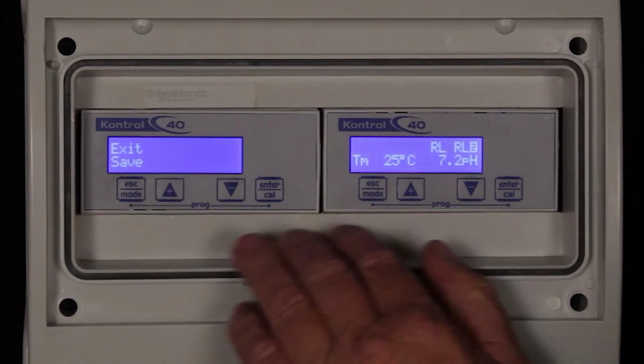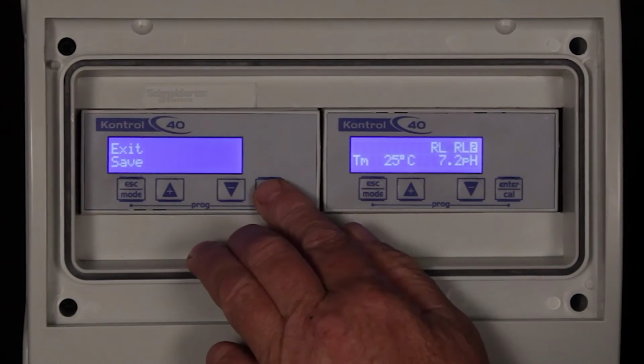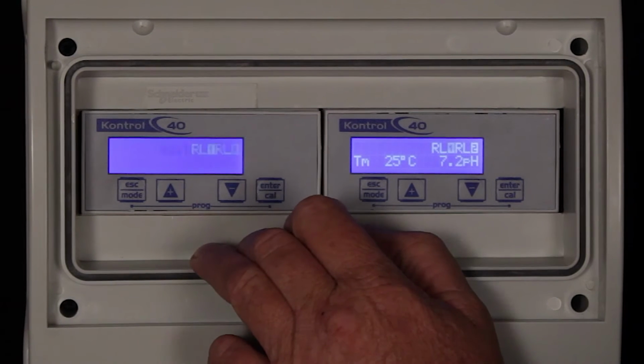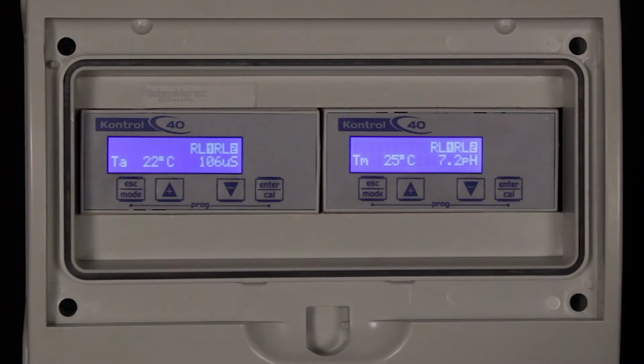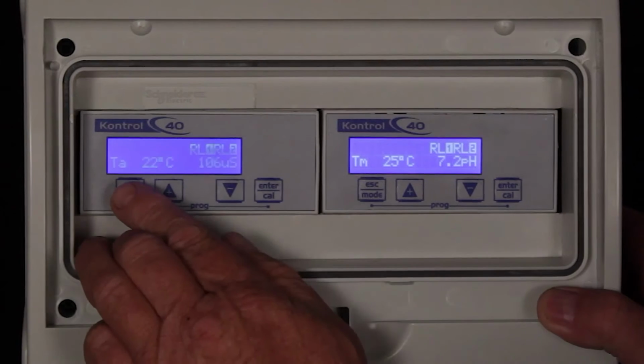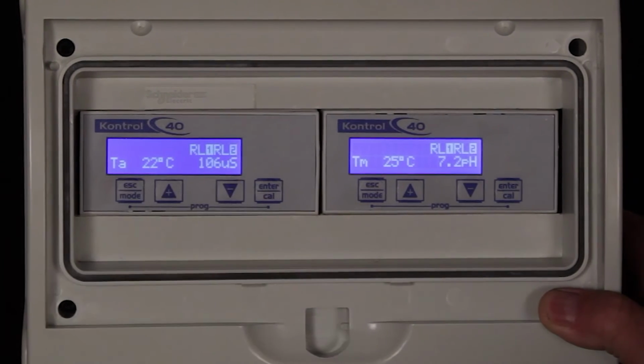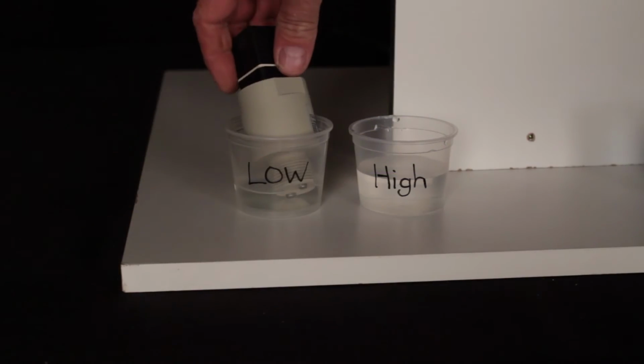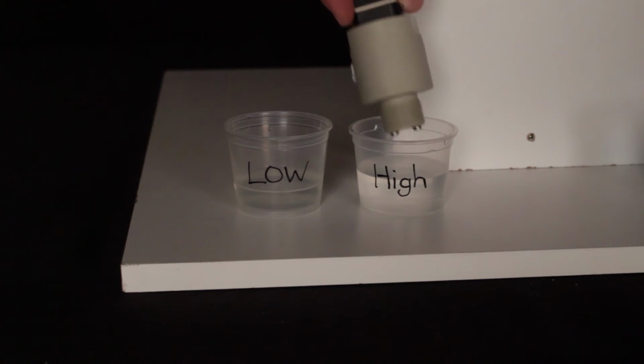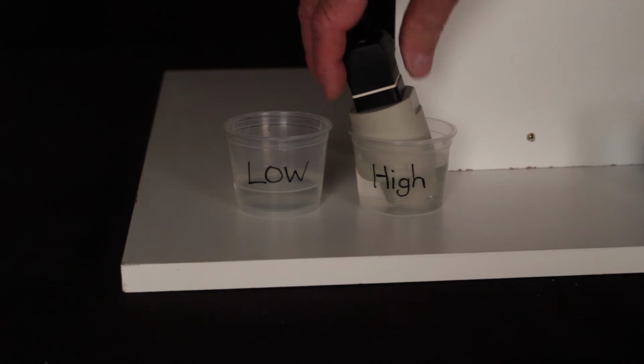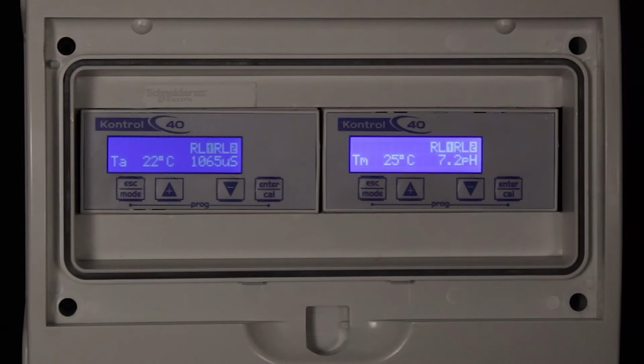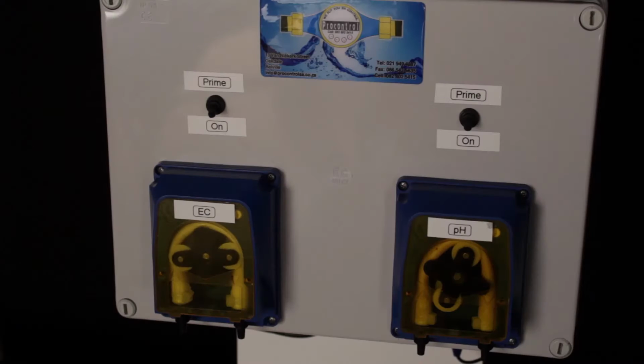Press the escape mode button until you get to the exit and save message. Now press enter to save all changes. The controller now indicates that the pump is on and the pump is running. Now when we move the probe to a higher solution than the set point, the controller will stop the EC pump. When the EC has reached its set point, it will allow for the pH pump to switch on if it is required to do so.